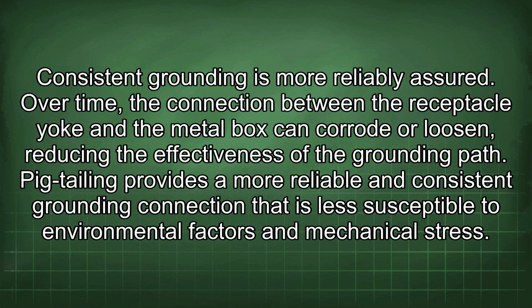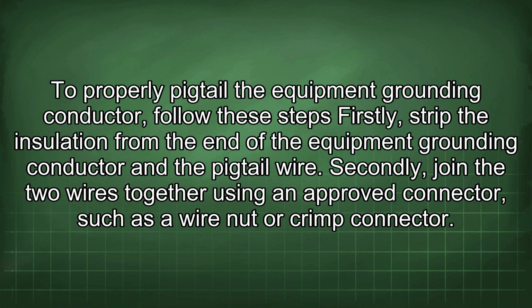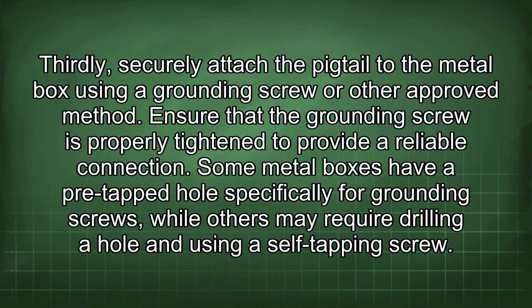Over time, the connection between the receptacle yoke and the metal box can corrode or loosen, reducing the effectiveness of the grounding path. Pigtailing provides a more reliable and consistent grounding connection that is less susceptible to environmental factors and mechanical stress. To properly pigtail the equipment grounding conductor, follow these steps. Firstly, strip the insulation from the end of the equipment grounding conductor and the pigtail wire. Secondly, join the two wires together using an approved connector, such as a wire nut or crimp connector. Thirdly, securely attach the pigtail to the metal box using a grounding screw or other approved method. Ensure that the grounding screw is properly tightened to provide a reliable connection.